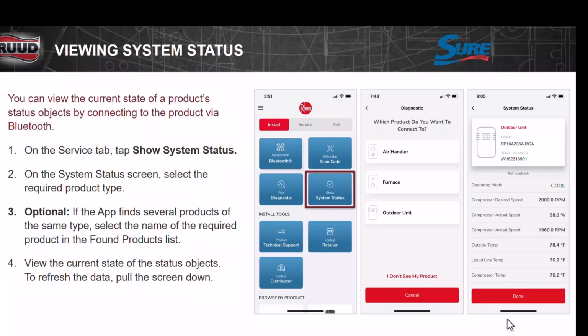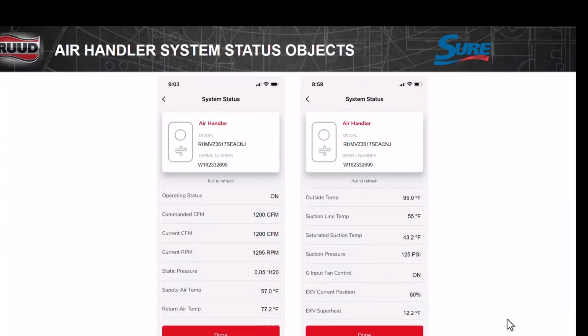We can see that our compressor desired speed is 2,000 RPMs, and our compressor actual speed is 1,980 RPMs. So we're running pretty close to what it shows it needs to be at. Our outdoor temperature is 78, our liquid line temperature is 70.2, our compressor temperature is 70.2. Looking at the air handler, it's telling us what the unit is commanding the airflow to be: 1200 CFM, and the airflow is 1200 CFM. Our current RPM is 1295.